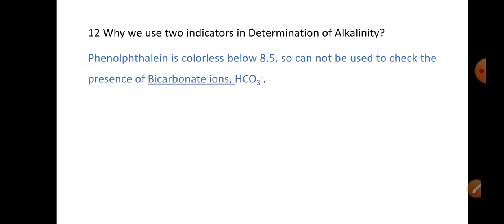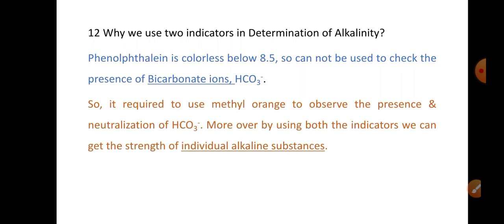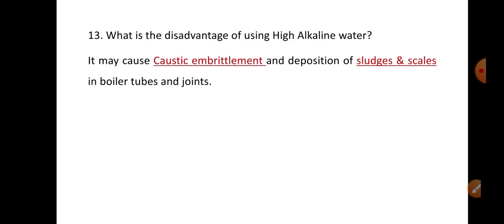Why do we use two indicators in the determination of alkalinity? This is because phenolphthalein is colorless below pH 8.5, so it cannot detect the presence of bicarbonate ions; methyl orange is required to observe the neutralization of bicarbonate. Using both indicators allows us to determine the strength of individual alkaline substances. What is the disadvantage of using highly alkaline water? It may cause caustic embrittlement and deposition of sludges and scale in boiler tubes and joints. It is therefore important to check the alkalinity of any water sample before feeding it into a boiler.